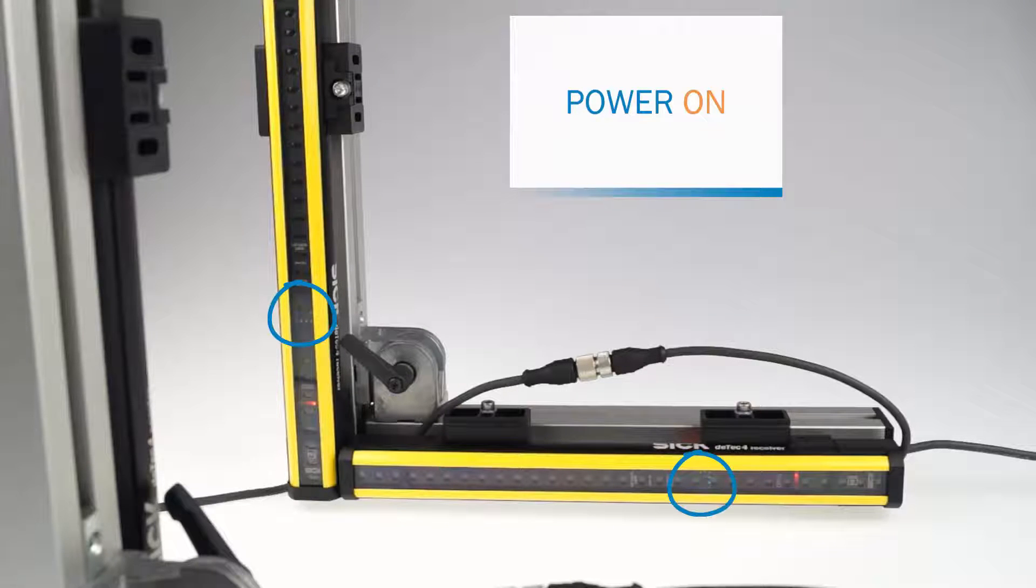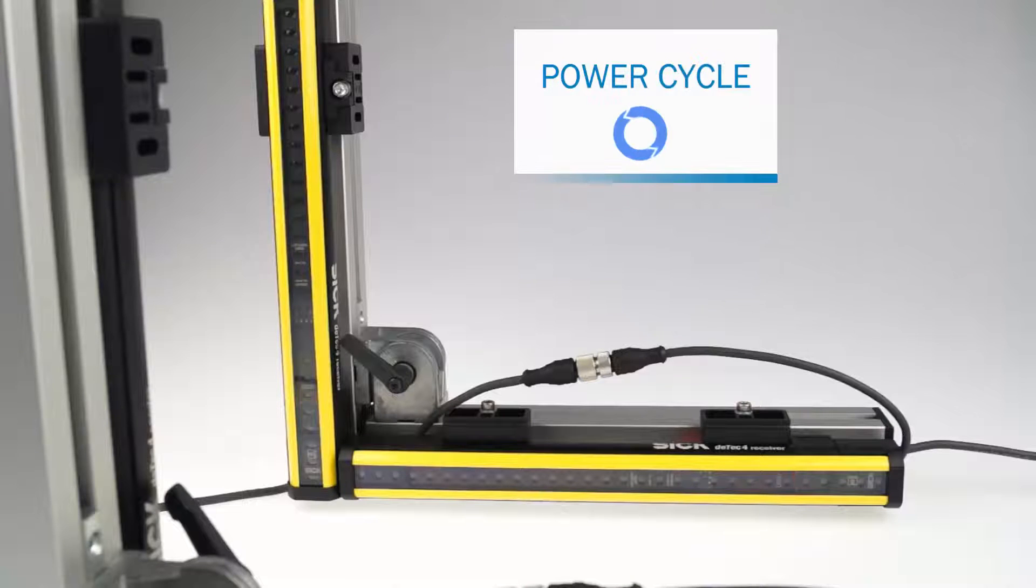Additionally, the blue alignment LED 2 is flashing to show that the host-guest cascade is configured. In case of a host-guest-guest cascade LED 2 and LED 3 would flash blue. After another power cycle, the light curtains are cascaded and fully operational again.